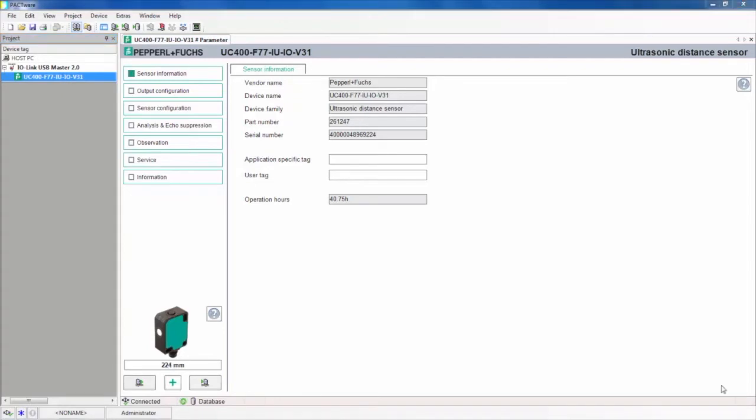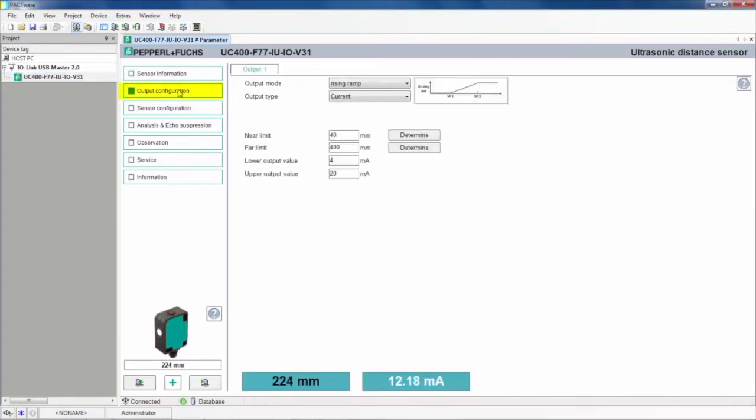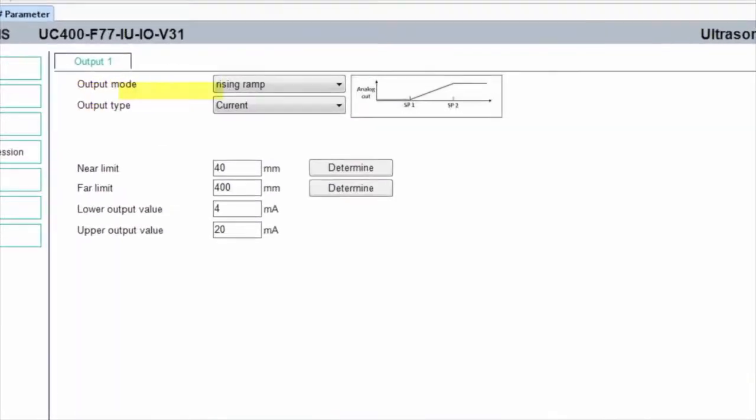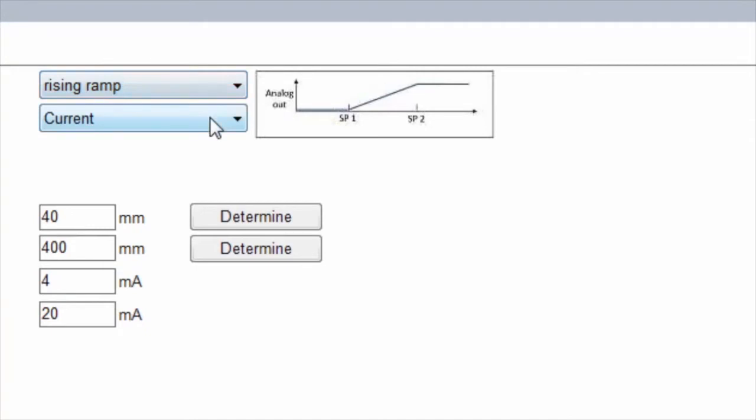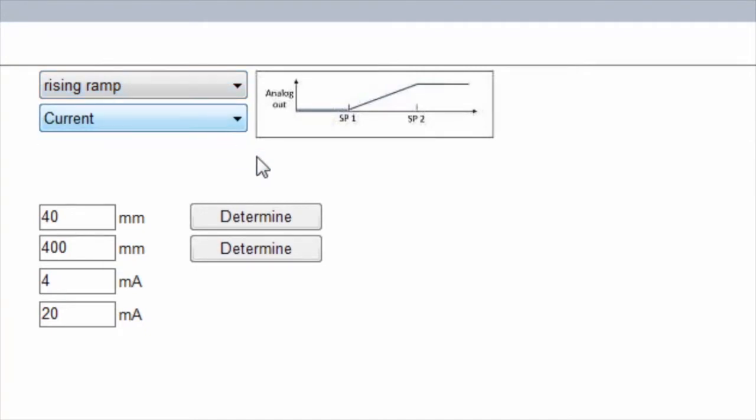In the Sensor Parameters panel, there are seven different tabs. Most of them are pretty self-explanatory, so I'm only going to highlight a few of the unique application solvers. First, let's look under the Output Configuration tab. Here, with an analog sensor, you can select a rising or falling ramp and a current or voltage output. You can also enter the numeric near and far sensing limits in millimeters or click the Determine icon, and that will automatically determine the limits based on an actual target position.